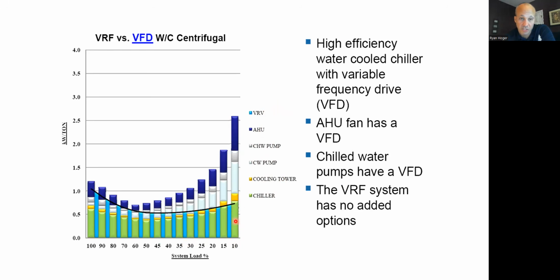So in this case, green is the chiller. If I look at the green and the blue lines, it's like, wow, these are really similar efficiencies. And in fact, this chiller is better than the VRF. I should probably buy a chiller, right? But wait, I got to take the gold color, yellow, and add in the cooling tower energy for that cooling tower fan. Then I got to take the condenser water pump in white and add that on. And then I got to take the chilled water loop pumping system and add that on. Then I got to, in dark blue, take the fan energy for the air handler and add that on. And all of a sudden, VRF could be significantly more efficient than the whole entire chiller plant.